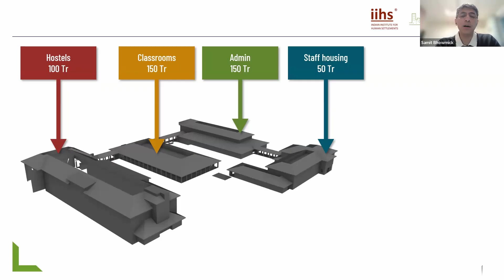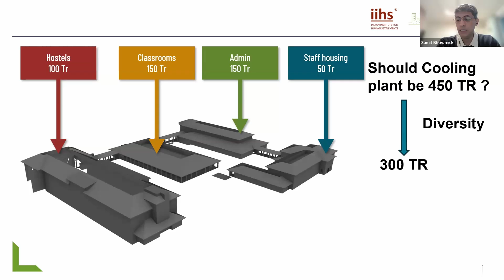luckily we have this benefit of diversity, which, like I said, is very frequently overlooked. And by diversity, we mean the reality that buildings do not operate at peak loads at all points of time. So we expect, for example in this case, the hostels and the staff housing to not be fully operational during the daytime, and therefore 450 tons could be properly sized to 300 tons.